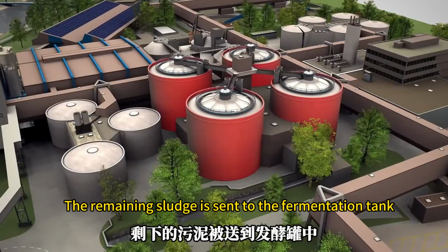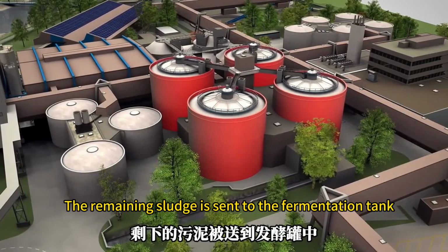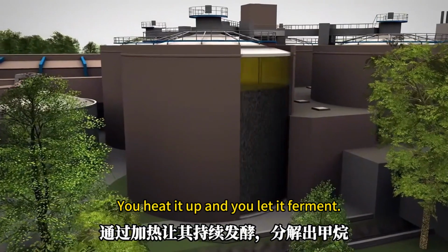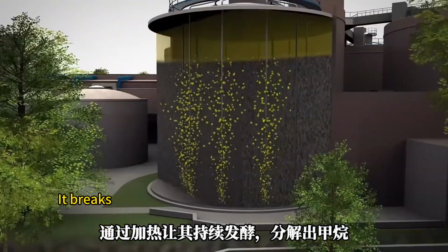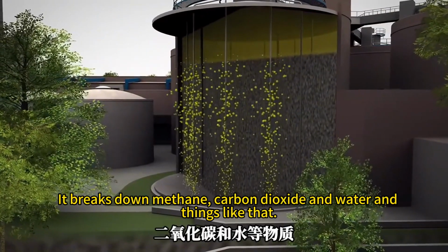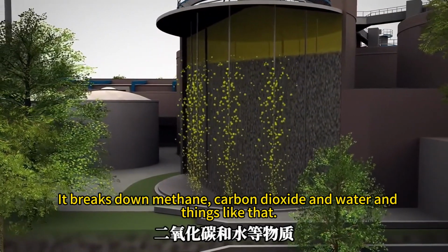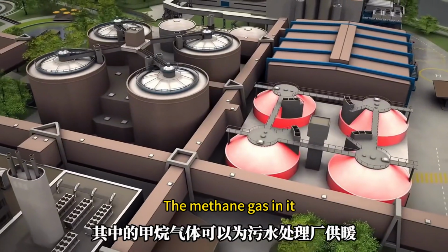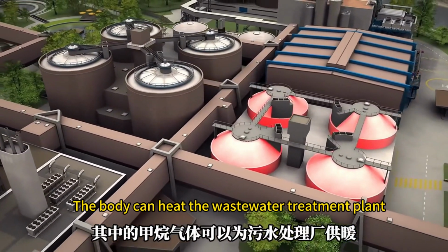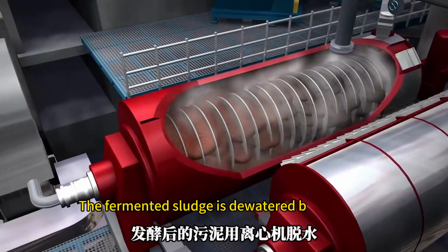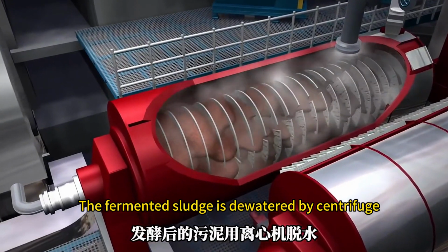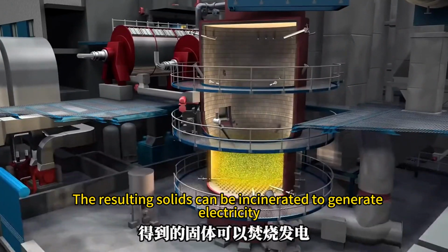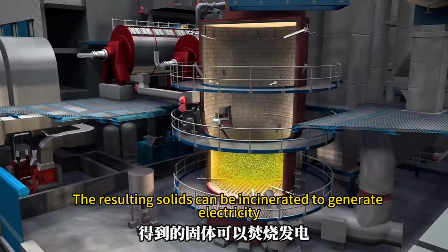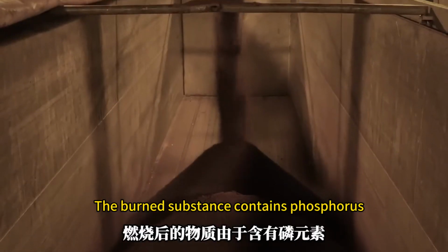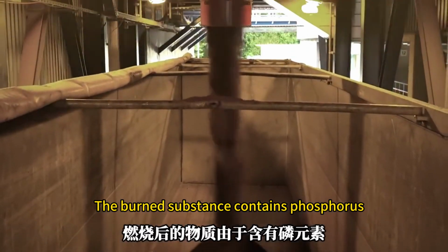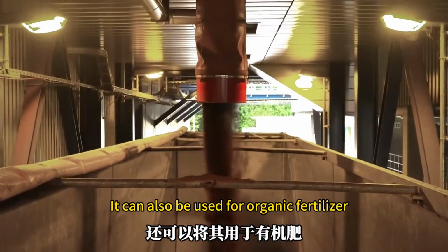The remaining sludge is sent to the fermentation tank. You heat it up and let it ferment. It breaks down into methane, carbon dioxide and water and things like that. The methane gas in it can heat the wastewater treatment plant. The fermented sludge is dewatered by centrifuge. The resulting solids can be incinerated to generate electricity. The burned substance contains phosphorus. It can also be used for organic fertilizer.